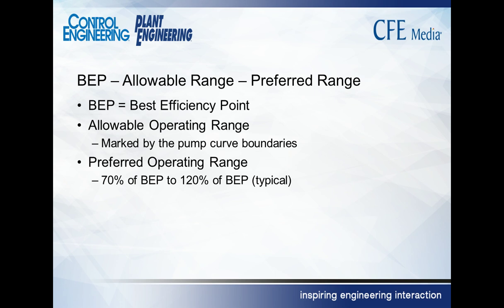So the best efficiency point is one of the focal points of the information presented on the pump curve. In addition to the best efficiency point, there is the allowable and preferable operating range. Everybody would like to, but it's going to be difficult to get a pump sized so it matches perfectly with the best efficiency point. And in fact, the flow may change and the head may change throughout the operation, especially if it's pumping, for instance, out of a sump where the sump level is changing.